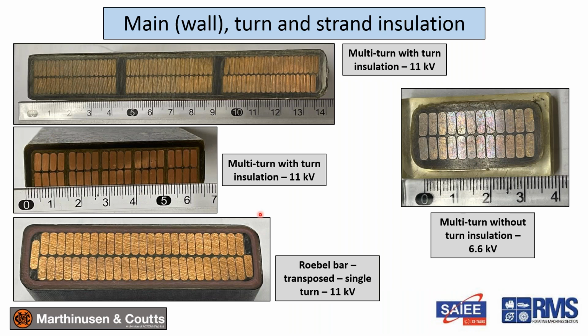So now we get on to, back to the same slides, but we look at the difference between main wall, turn, and strand insulation. Your main wall insulation is here. Your turn insulation is this insulation here, or on modern machines, it's the insulation between these strands here. So in other words, they don't use dedicated strand insulation like this, for example. They rely on the strand insulation to be the turn insulation. And then that Roebel transposed single turn design that we saw there of 11 kV.